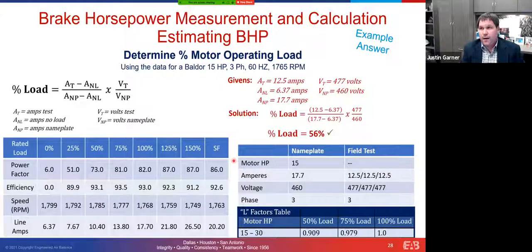Now, I do know that there are applications, especially in the HVAC industry nowadays, where motor manufacturers rate their motor off the shelf for a certain condition, but when you put it into a conditioned airstream inside of an air handling unit, they will actually uprate their motor. Say in this particular case, we have this 15 horsepower motor, but we're going to put it into an air handling unit in a draw-through application, so it's downstream of the cooling coil. The motor manufacturer then knows it's always going to have cold air blowing across it. At that point, they may uprate that motor to 17 and a half horsepower. And they'll actually allow the air handling unit manufacturer to use their motor at an increased wattage, so to speak, because of the application.